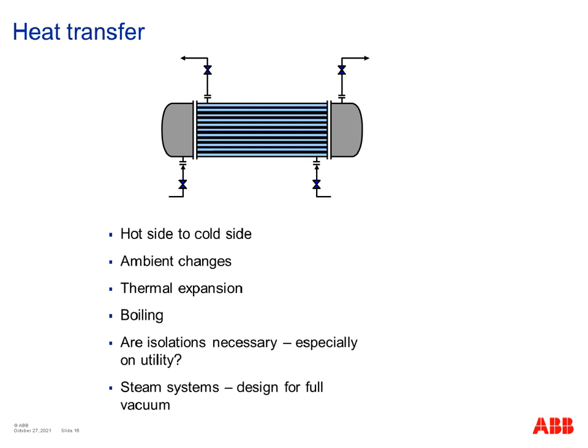If you do have the cold side being heated in this case, you could have thermal expansion of the liquids, or you could also have enough energy input to boil the liquids, which will obviously then lead to vapor and quite a quick rise in pressure. So that's normally going to be more onerous than the thermal expansion case. In the schematic on the slide, we've got isolation valves showing on both the inlets and outlets to the shell and the tube side of the exchanger.